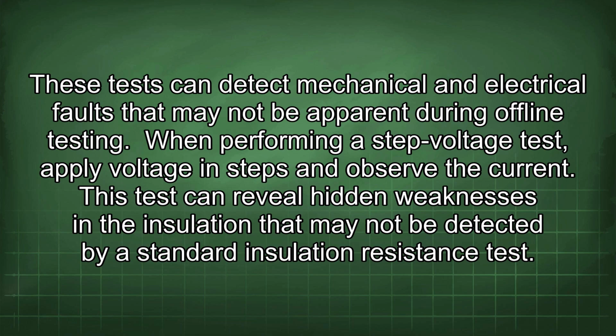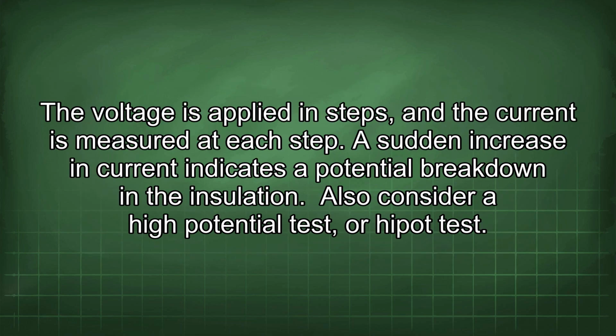When performing a step voltage test, apply voltage in steps and observe the current. This test can reveal hidden weaknesses in the insulation that may not be detected by a standard insulation resistance test. The voltage is applied in steps, and the current is measured at each step. A sudden increase in current indicates a potential breakdown in the insulation.